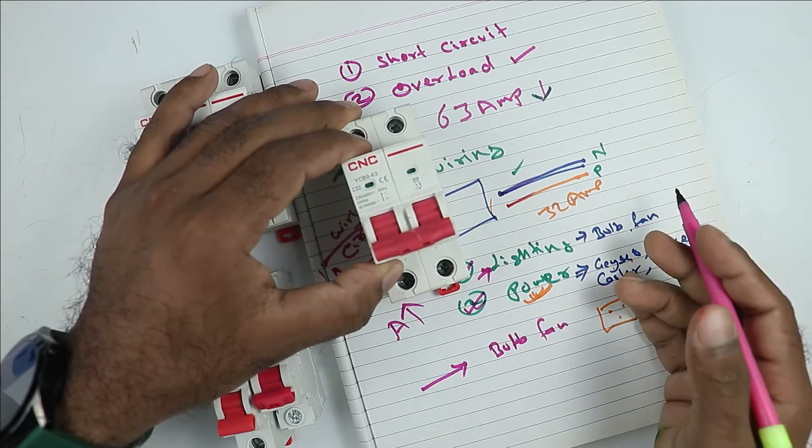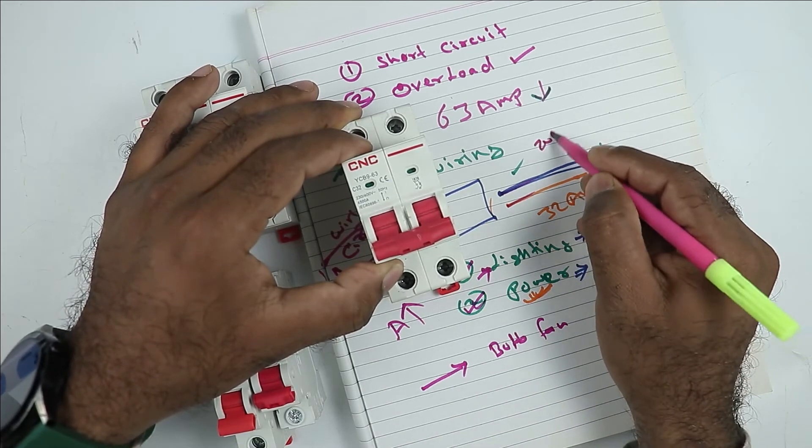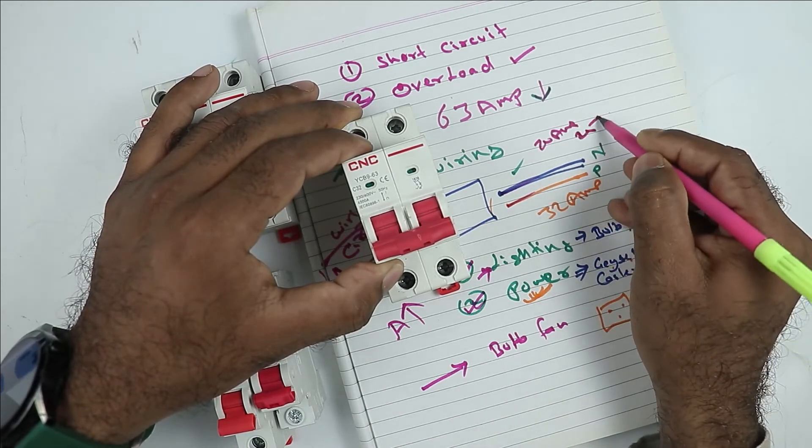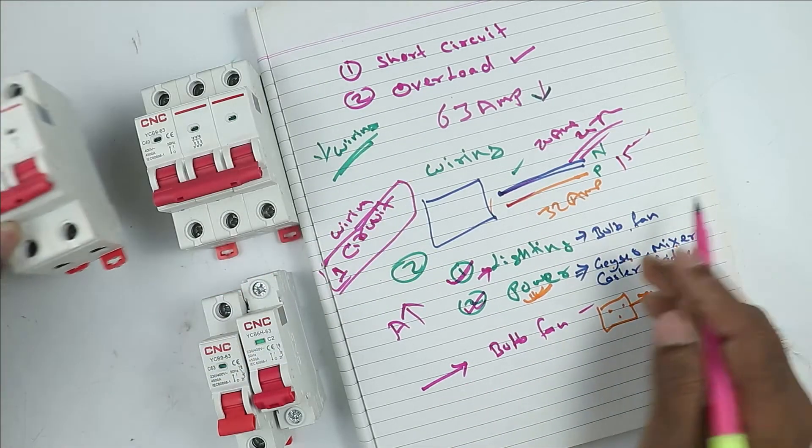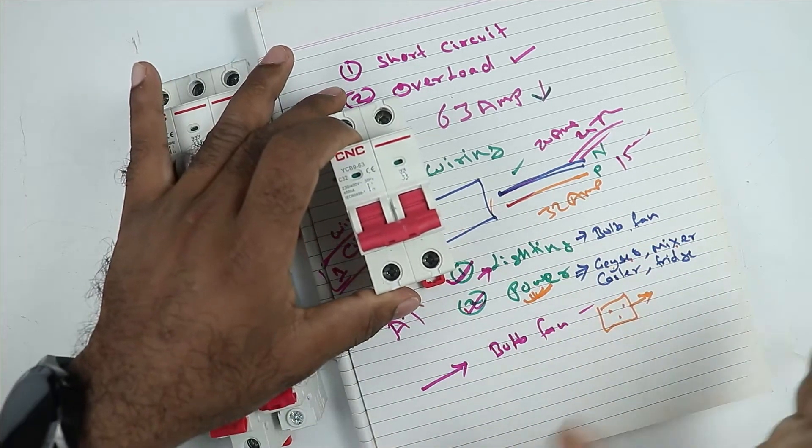I mean when this much load is running, the current will be around 20 ampere or it can be 25 ampere. This will be the highest. So if the whole load is running, then this MCB will provide the protection.